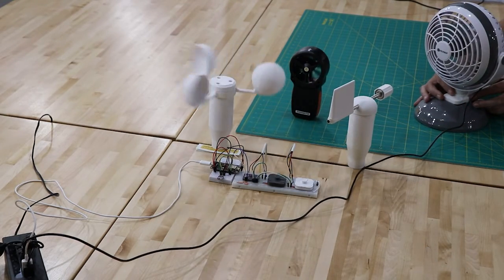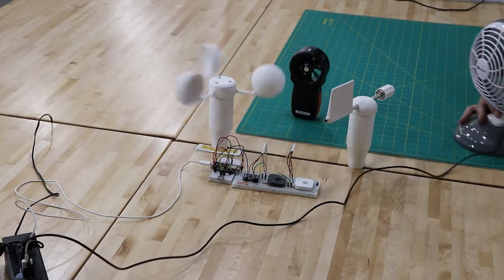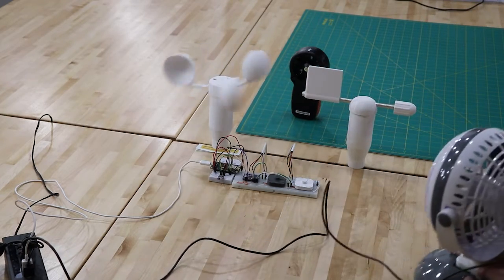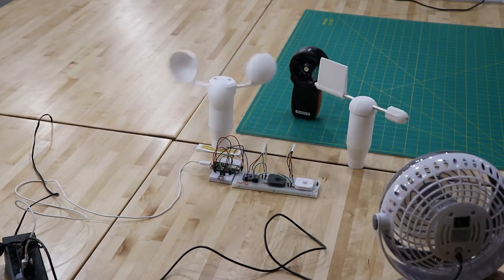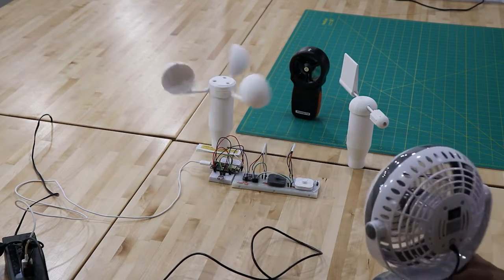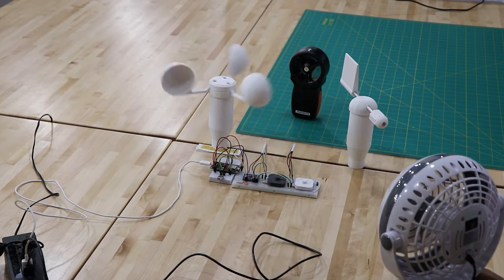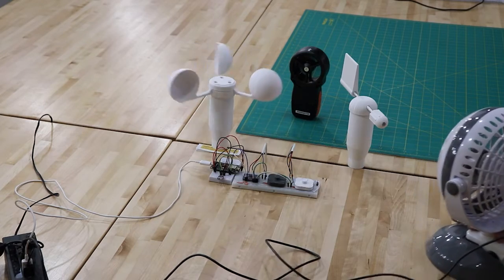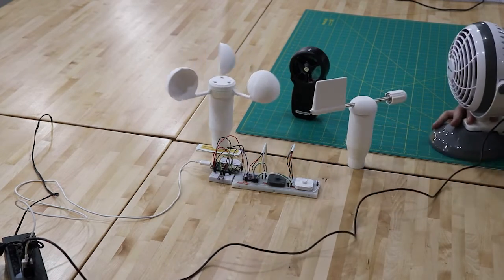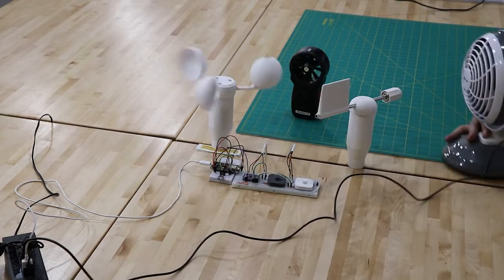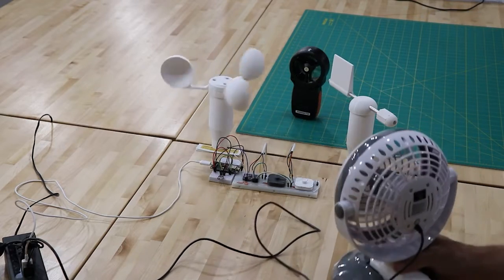During this initial testing, I noticed there was a critical value of airspeed that would start the anemometer rotating, as well as turn the wind vane in the direction of flow. It takes about 1 meter per second to get things moving, which is equivalent to the breeze generated by walking. Even though a lot of thought has gone into minimizing friction, there is still some present in the system.